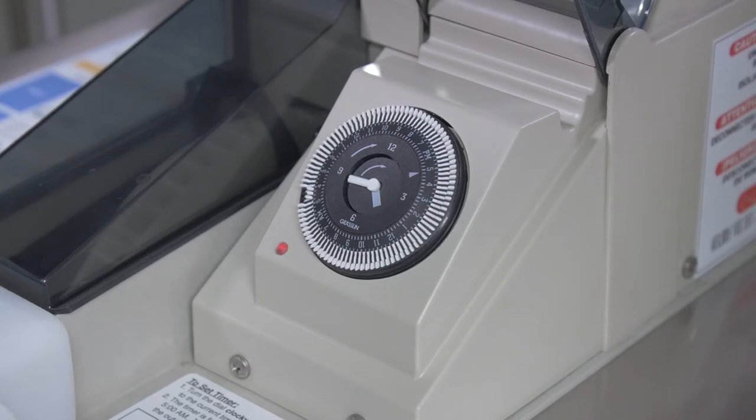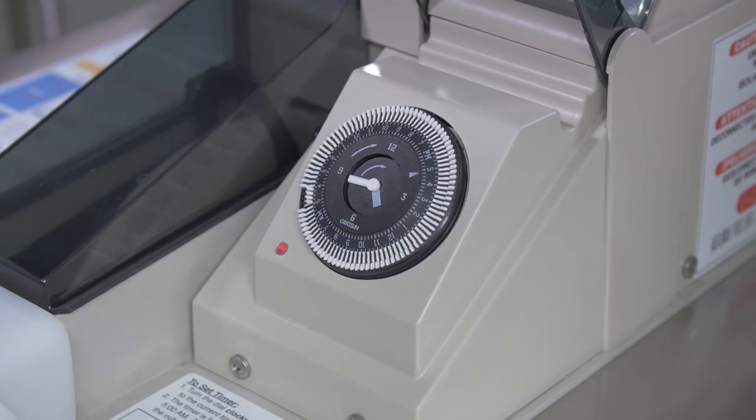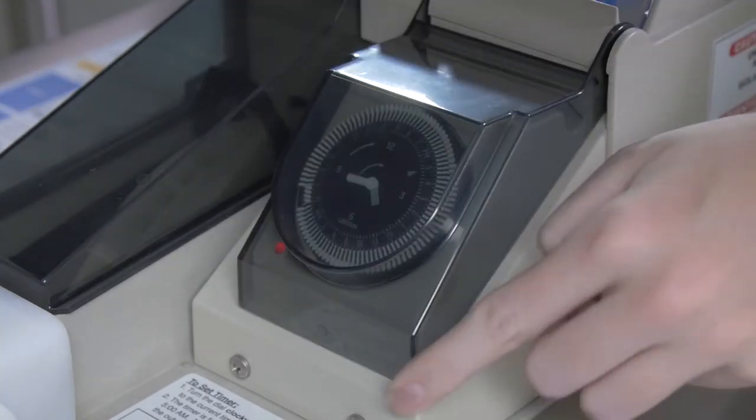If there is only grease in the collector, increase the run time by moving one tab from the outer to inner position. Repeat this process until you find the optimal run time for your kitchen.